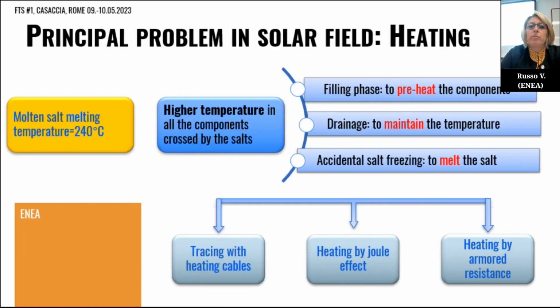Okay, let's start with the principal problem related to the melting temperature of the molten salt. As we know, this value is equal to about 240 degrees centigrade. So it is mandatory to keep the temperature higher than this value in all the components of the plant, all the components crossed by the salt. And also during all the phases of functioning of the plant, for example, during the filling phases, in order to preheat the component, or during the drainage phase, in order to maintain the temperature higher than the freezing value of the salt. And also after an accidental salt freezing, in this case, in order to remelt the salt solidified in the component.